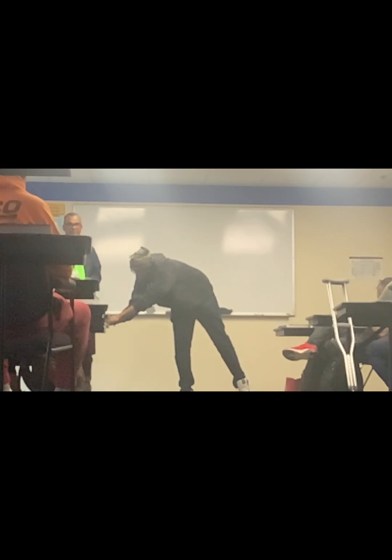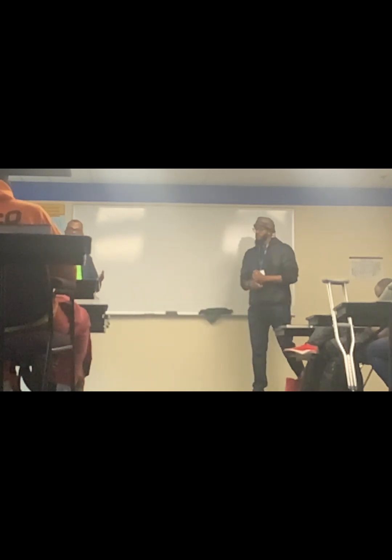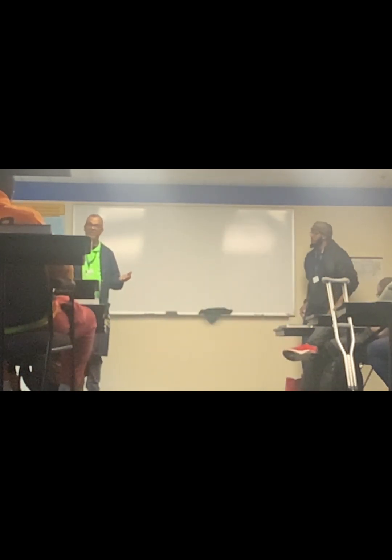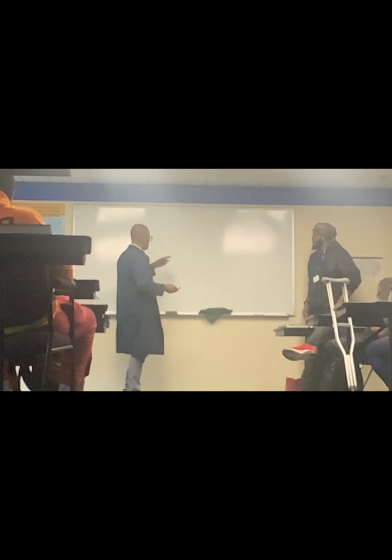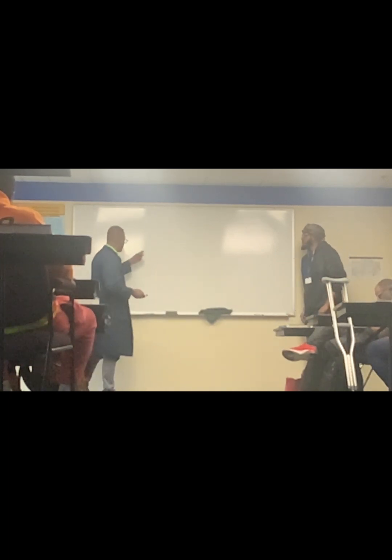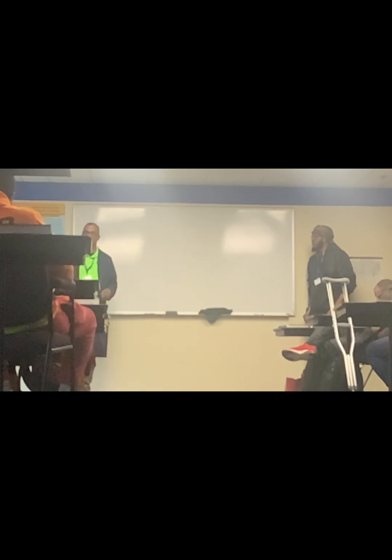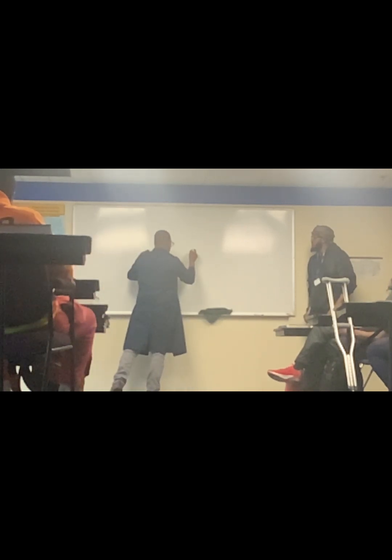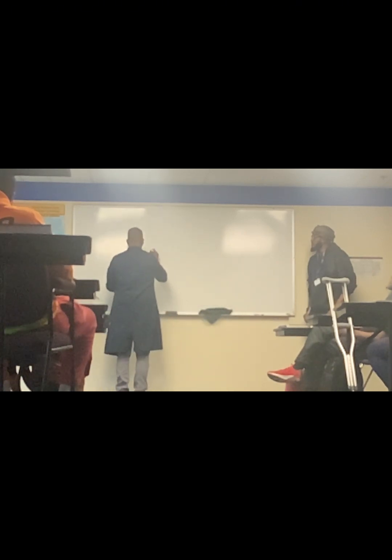15 was B, right? Line 1 and 2? Yeah. And the same thing if I go to the other one, to ground. As a matter of fact, that's one way you can test. If I have a 240 circuit and I go from here and here to get 120, and I go from here to ground and get nothing, what leg is messed up? L1. Line 1. That's the way you can test it. And then we already know if we go here, it should be 240, but we want to know which leg has died. Bam, bam, 120. Bam, bam, 0. It's you, buddy. And it could be you on a double contactor.